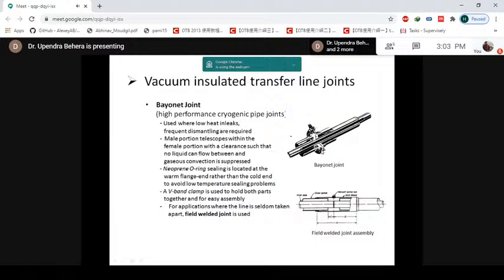And here the sealing is done at room temperature, and neoprene can be used, located at the warm flange rather than the cold end to avoid low temperature sealing problems. And V-band clamps are used to put it. These are all quick disconnect couplings. KF series of different sizes are generally used for all these.